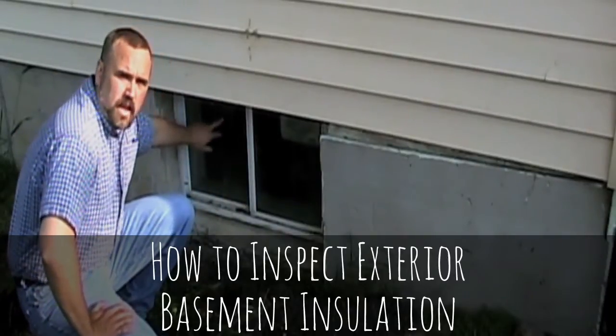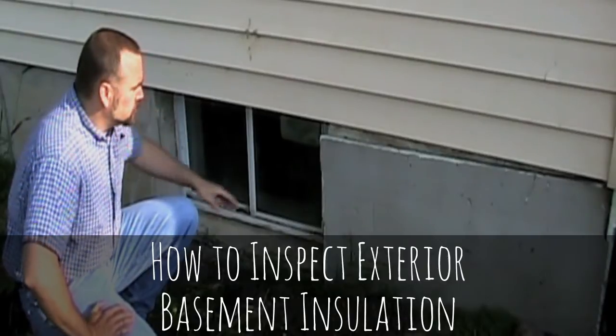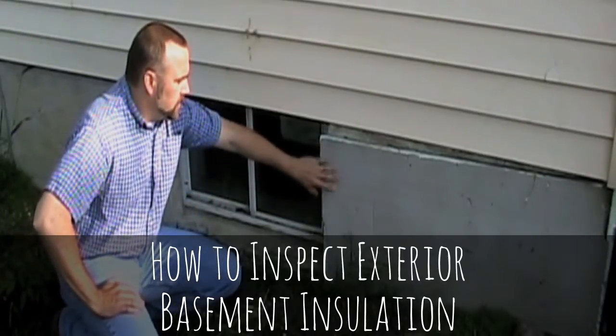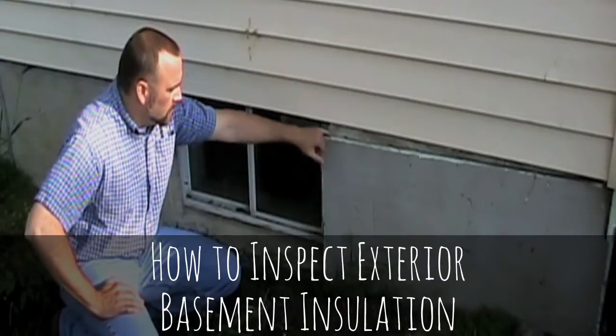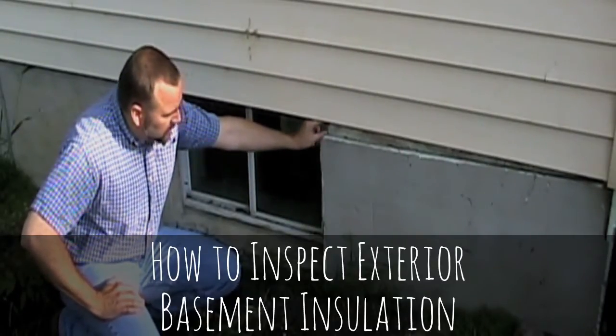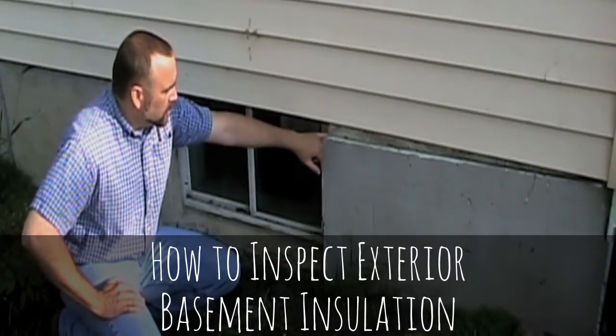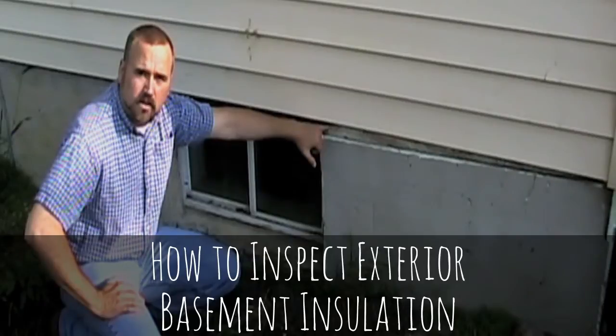This double pane window actually has more insulation value than a bare concrete wall. What they've done here is covered it with a concrete-type material so you can't see the rigid insulation in it, and it doesn't break down. But over time you can see where this insulation has settled, because they only have it right below the surface of the ground. So it's settled down — this is an obvious area for heat loss here.